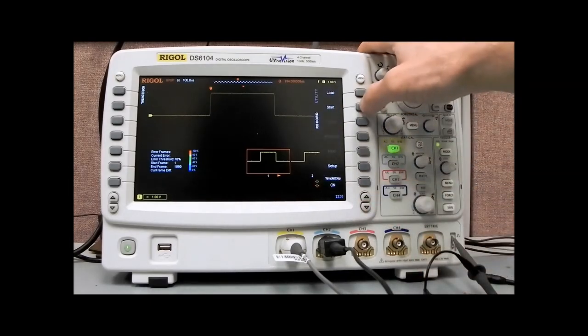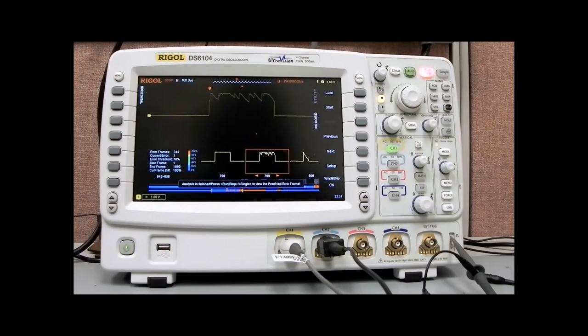Now we can analyze. We go to the second page and press Start, and it will analyze all of the other waveforms versus that golden mask. I'll let it run for a second. We're at 11.45, 18.90, and now it's actually playing through all of those waveforms. It says Analysis is finished. Press Run, Stop, Single to view. Now you can see we're at frame 799.